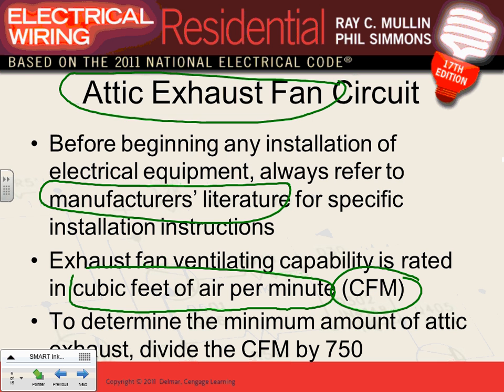How many cubic feet of air you want to exhaust out of the building or bring into the building? Air exchange and all this good stuff. So determine the minimum amount in the attic. The magic number you're going to take is to divide the CFM by 750. Well, when you go, there's a recommendation: if your attic is this amount, this is the size of the fan you want.